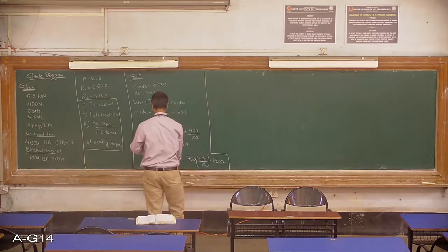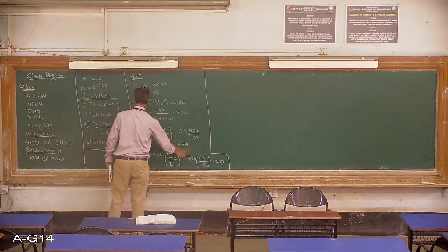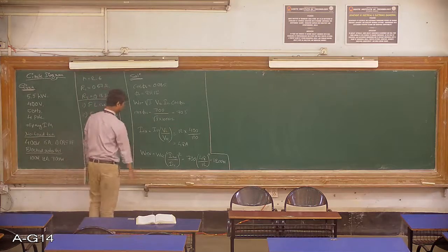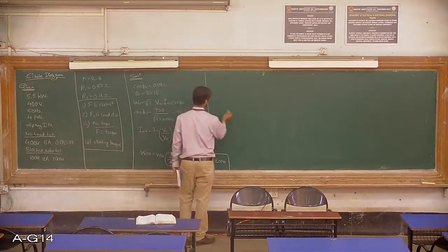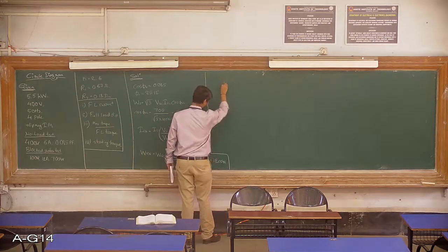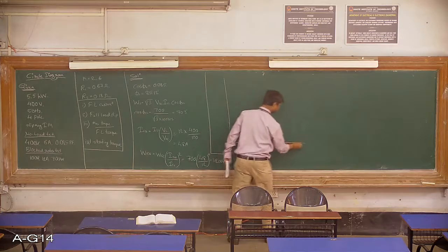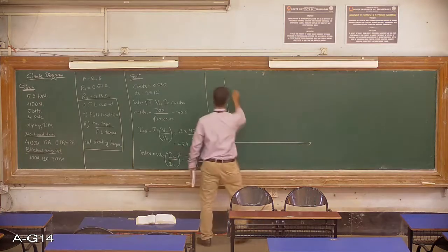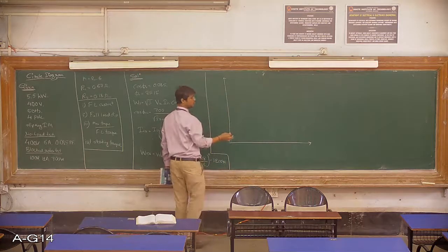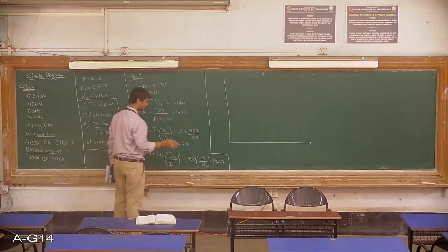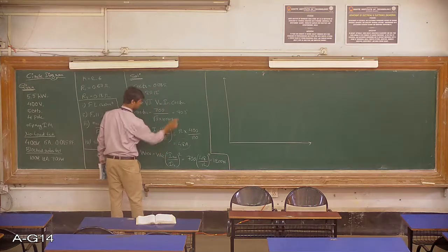Okay. After this, we now know the ISN, we know WSN. This much is sufficient to start plotting the graph. Selecting proper current scale, we can start. Now this is the graph page here. Since the actual graph page will be of hardly 20 to 30 centimeters, select the proper scale to accommodate this 48 amperes ISN into the graph page.